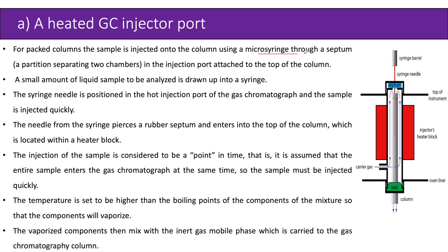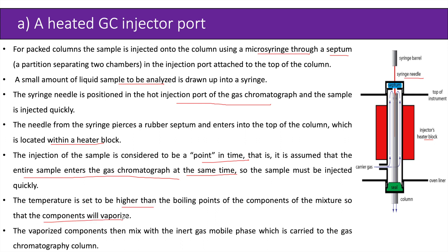For packed columns, using a heated GC injector port, the sample is injected onto the column using a microsyringe through a septum in the injection port attached to the top of the column. A small amount of liquid sample is drawn into the syringe, and the needle is positioned in the hot injection port and the sample is injected quickly. The needle pierces a rubber septum and enters the top of the column within a heater block. The entire sample is assumed to enter at the same time, so injection must be quick. The temperature is set higher than the boiling points of all components so they vaporize and mix with the inert carrier gas to be carried to the GC column for separation.